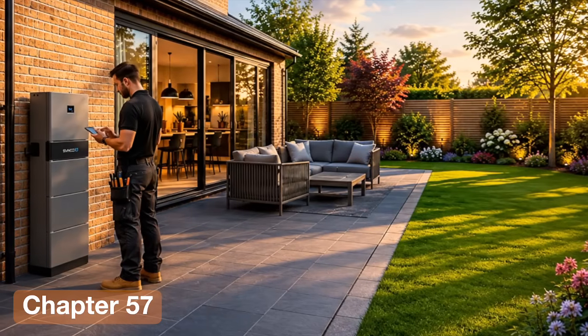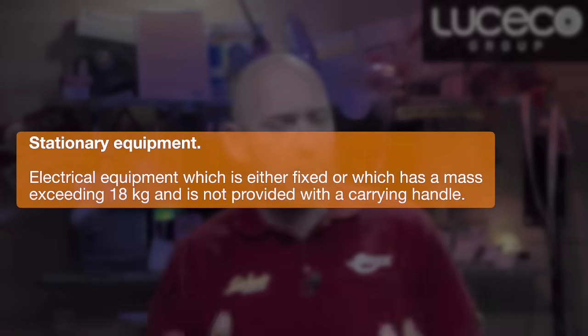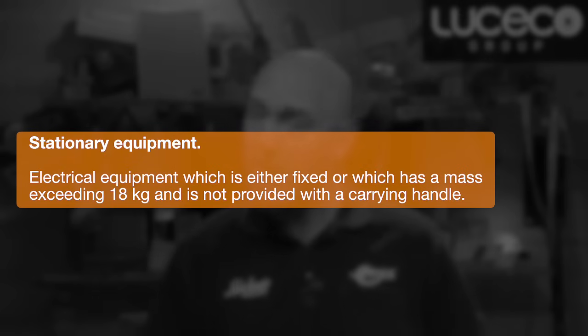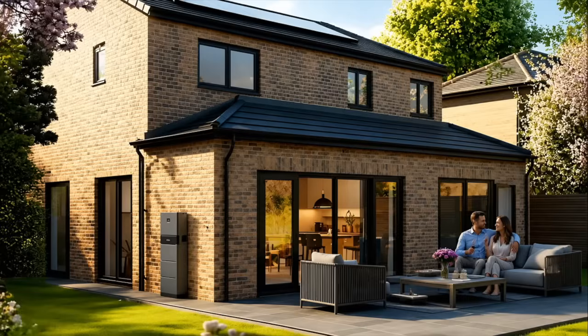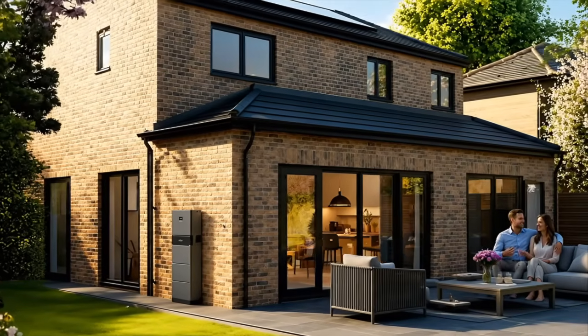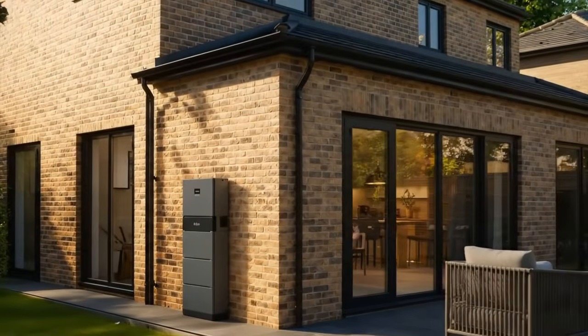BS 7671 now includes a dedicated chapter for stationary secondary batteries, which is Chapter 57. But what is a stationary secondary battery? A stationary piece of equipment, like a battery, is simply something that is fixed into place or heavy enough that it is not intended to be moved. Part 2 describes stationary electrical equipment as electrical equipment which is either fixed or which has a mass exceeding 18 kilograms and is not provided with a carrying handle. Then there's the term secondary battery. A secondary battery is one that can be recharged, so it can store energy and then release it back into the installation when it's required.